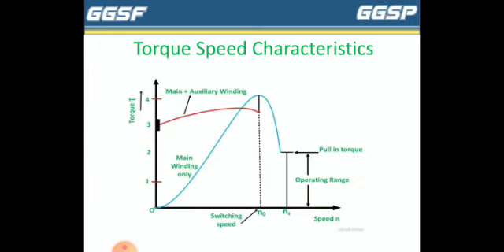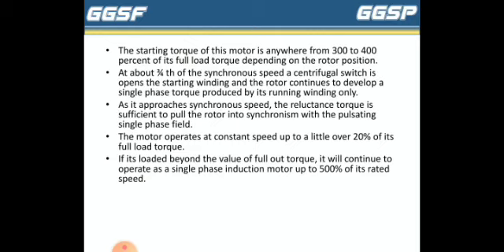This is the torque speed characteristic of the synchronous reluctance motor. The starting torque of this motor is anywhere from 300 to 400% of its full load torque, depending on the rotor position. At about 3/4 of the synchronous speed, a centrifugal switch opens the starting winding, and the rotor continues to develop a single phase torque produced by its running winding only. As it approaches synchronous speed, the reluctance torque is sufficient to pull the rotor into synchronism with the pulsating single phase field. The motor operates at constant speed up to a little over 20% of its full load torque. If it is loaded beyond the value of full load torque, it will continue to operate as a single phase induction motor up to 500% of its rated speed.